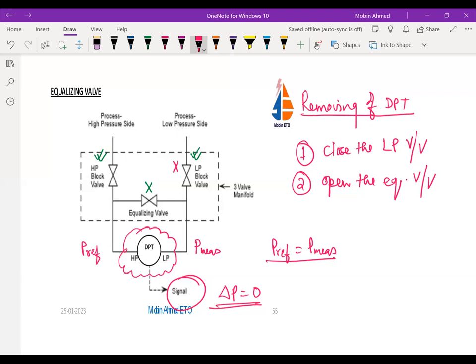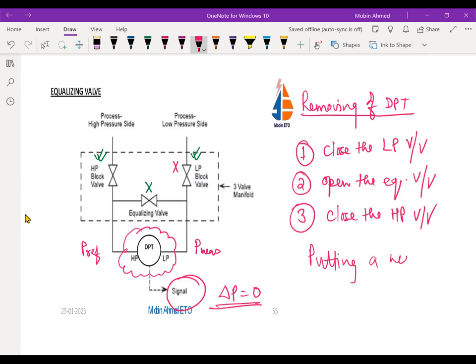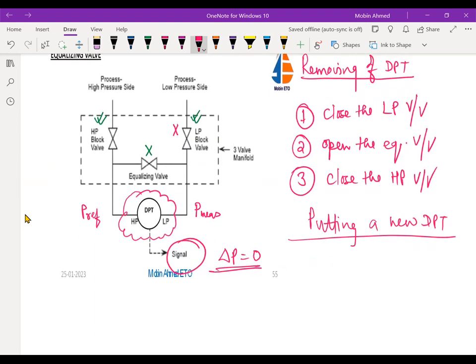So at this particular point, we are going to have 0 pressure. And that is the reason why we use this equalizing valve during opening. Otherwise, we are going to damage this. The diaphragm is there, that is going to get damaged. Then the third, close the HP valve. Close the HP wall. Okay. Now, how to put the DPT into service, we need to put it back. So putting back or putting a new DPT, because you open it for some maintenance purpose and again you are going to put it back.